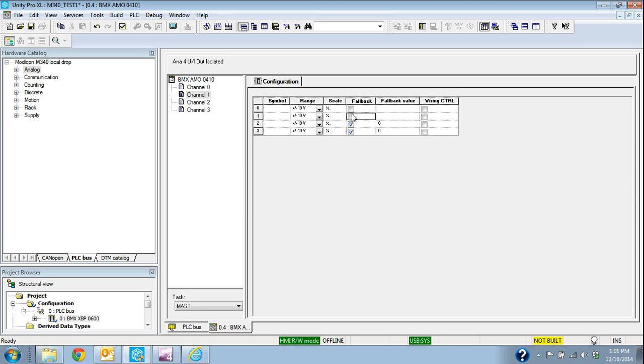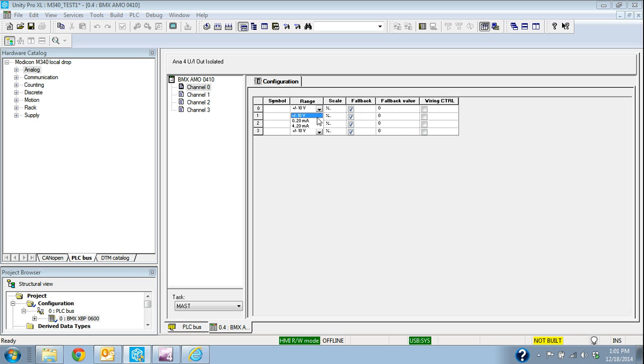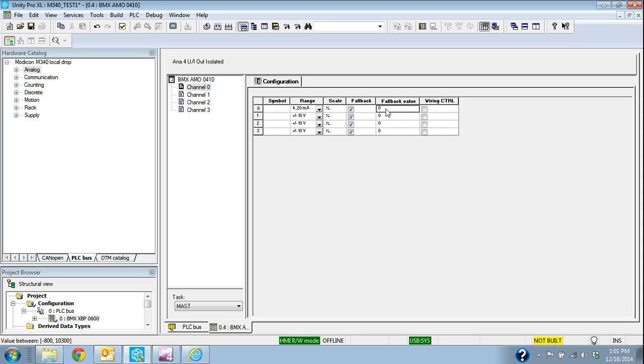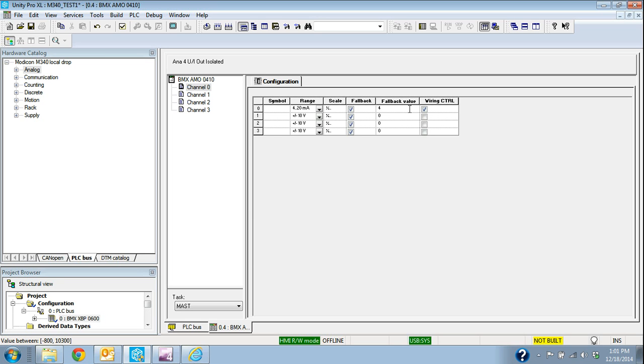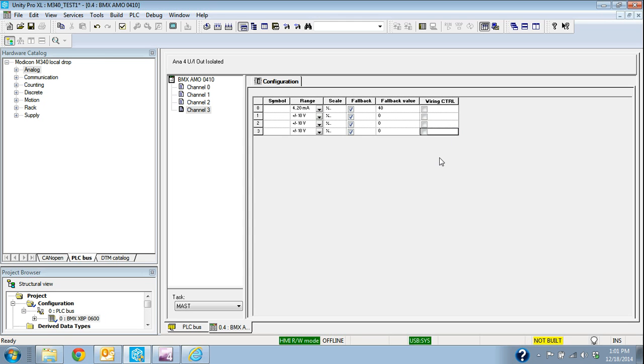I also have a fallback here, so if it loses communication, do I want it to go to 0? I'll say if I selected 4 to 20 and said no, if something should happen, I want this to fall back to some other value besides 0, and I would put the value in there. In this case, we'll put 40, and it would fall back to that instead of going to 0. That's where we'd find that configuration.